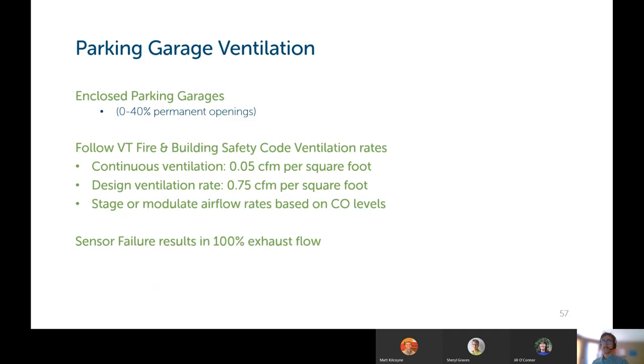Parking garage ventilation. This is a new call out in the code. An enclosed parking garage is a garage that has between 0 and 40% permanent openings within it. The code states that you must follow the Vermont Fire and Building Safety Code ventilation rates, which state that you need to have a continuous ventilation rate of 0.05 CFM per square foot of garage area. And the ventilation system must be able to reach 0.75 CFM per square foot at design rate. And you need to have carbon monoxide sensors throughout the garage that will sense the levels of CO and stage or modulate the airflow between the continuous rate and the design flow rate throughout the parking garage.